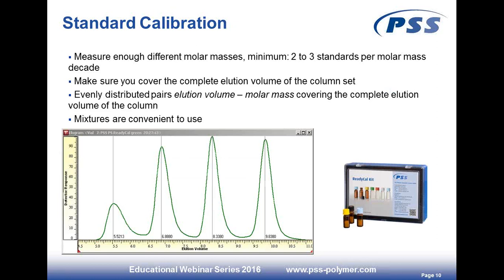The ReadyCal standard vial contains four different molar masses and gives four elution peaks in one injection, each assignable to a molar mass. When creating a calibration curve, you must calibrate over the whole elution volume of the column, use two to three standards per molar mass decade, and ensure the elution volume–molar mass pairs are evenly distributed over the column's elution volume.